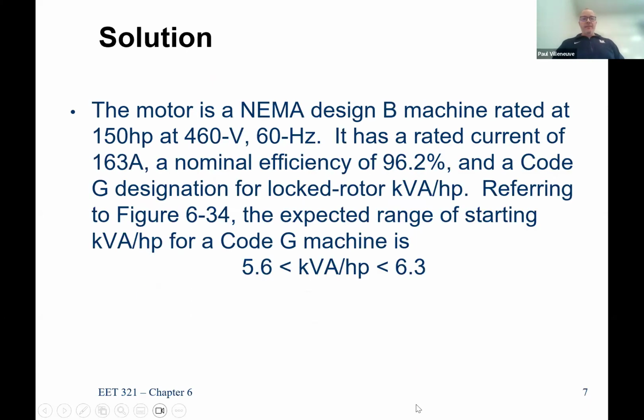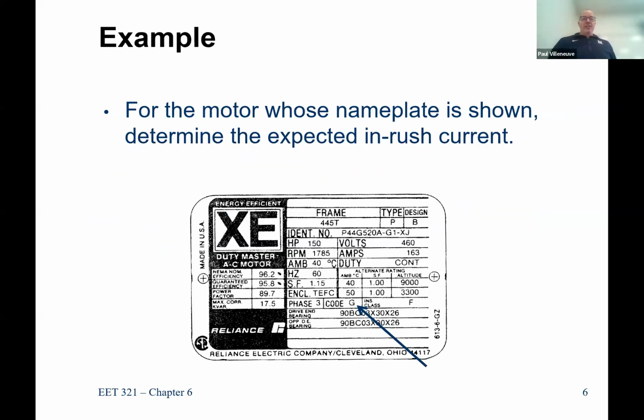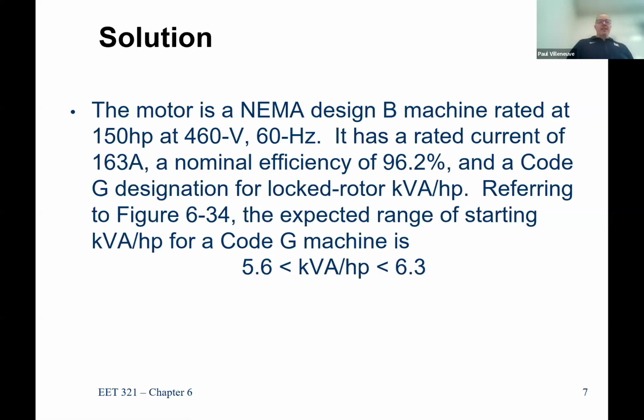So this over here. The motor on the previous one, it's NEMA Design B, which again just tells me the operating characteristics. It has 150 horsepower at 460 volts, 60 hertz. It has 163 amps and a nominal efficiency of 96.2%. Let's go back up to that. So this is an energy efficient Reliance motor, right? So pretty good, 96%. Now in this one, it has a kVA code G.